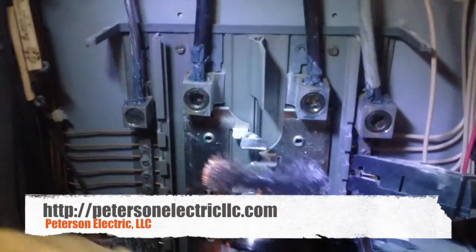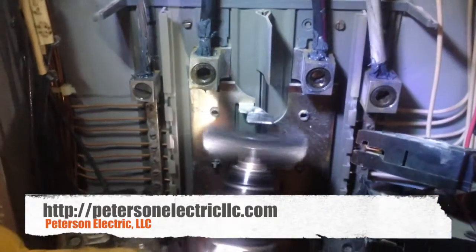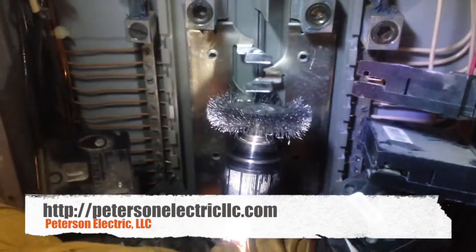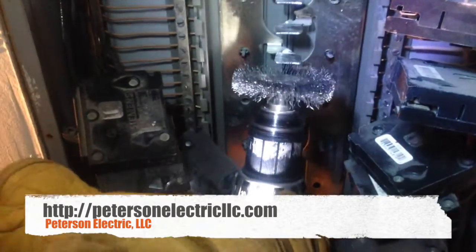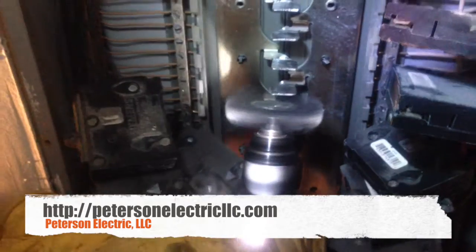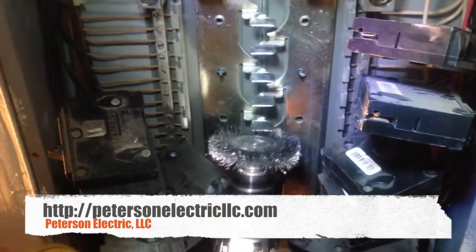You can see in here some of the acidicness going on inside of this panel. We know this panel is dead — I've already tested it. If this panel was not dead, you'd blow yourself up pretty sky high with this going phase to phase like that. We're going to get in here and do what my dentist does — we're going to clean off some plaque.